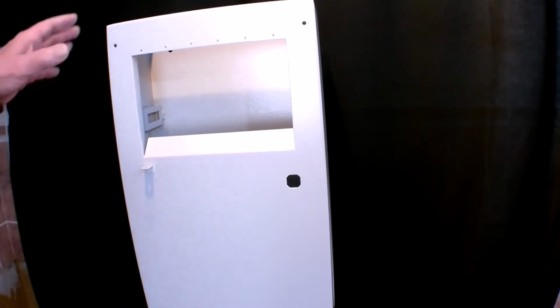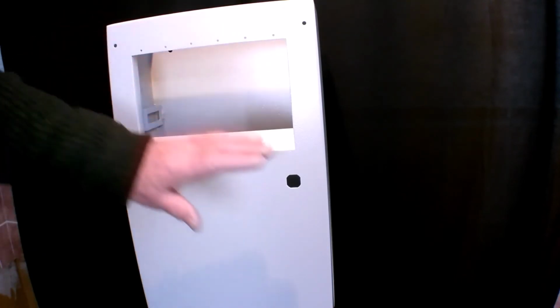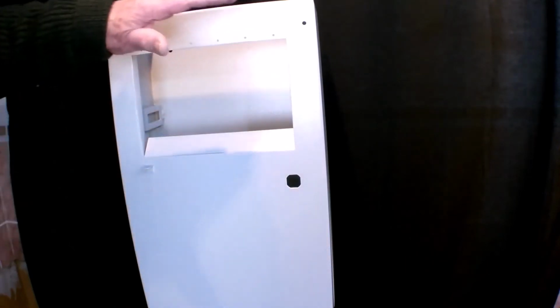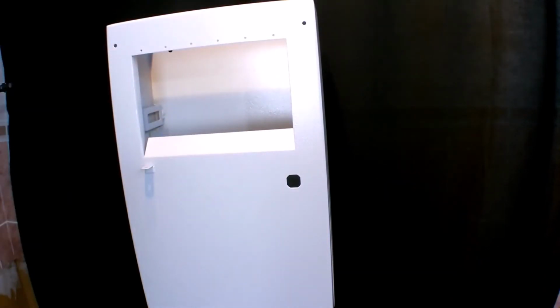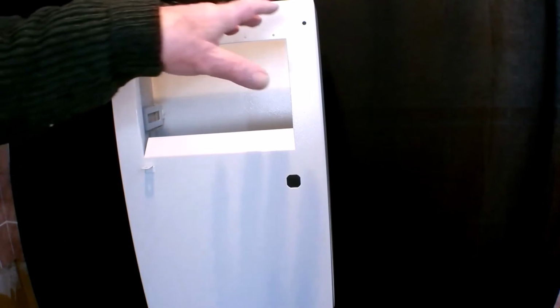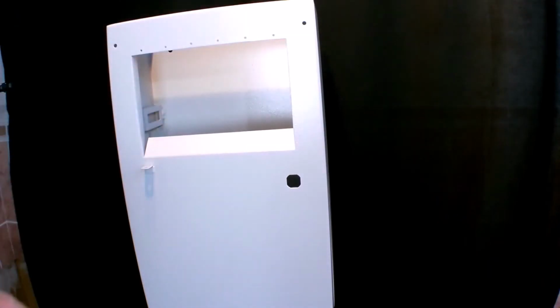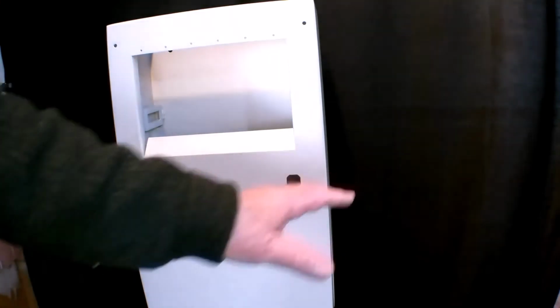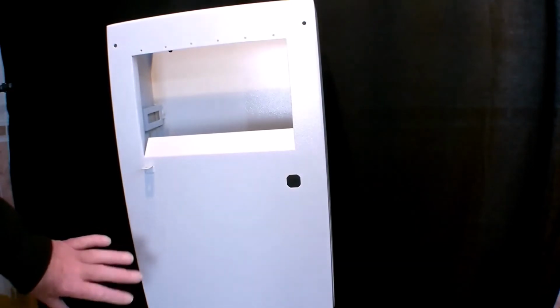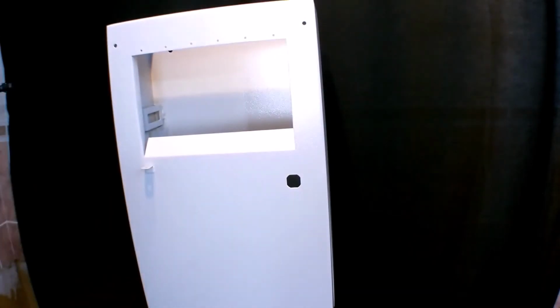We then make a 25 module unit wide in a single row, the same height as this. That will give you enough room for 7 contactors across the back, plus a couple of small relay units if you need them, or power supply. It has a nice versatile front. Again, it will take 2 thermostats if you need them. And then there is a double height one of those where you can get 4 thermostats, and again 7 motor starters across the bottom, and you can get 14 switches on the bottom.